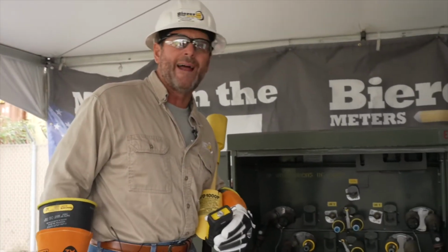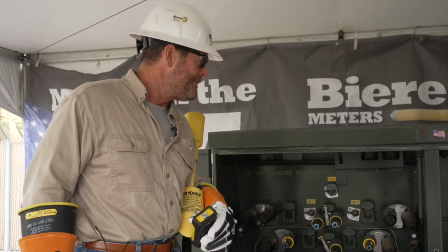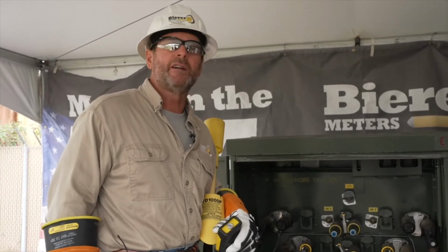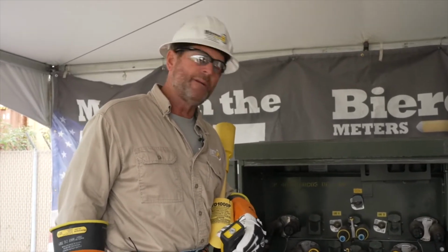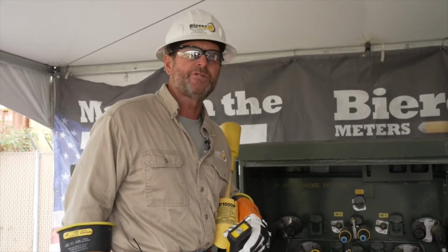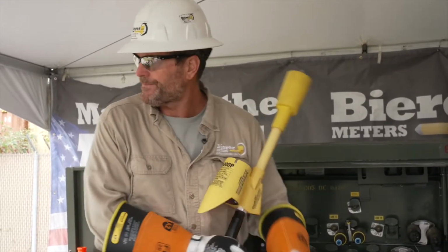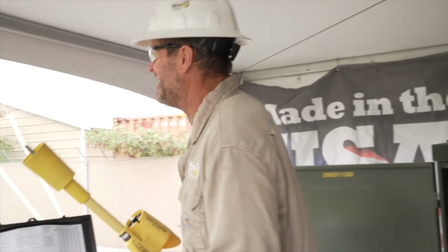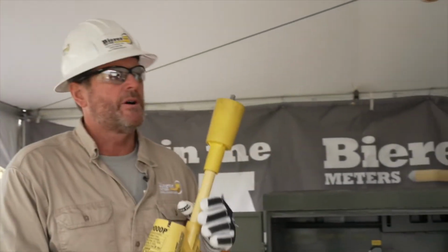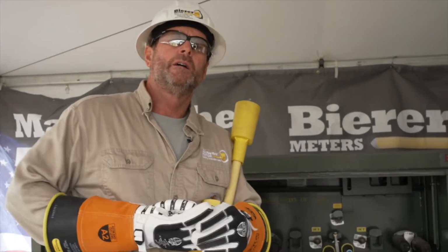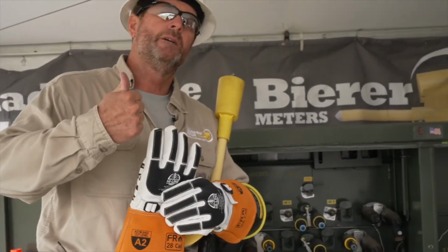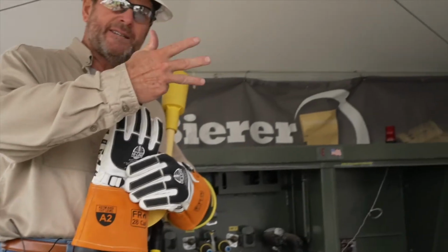Now you can take your TPGs and install your temporary protective grounds. Set up your EPZ, your bracketing, whatever you need to do to protect the equipment and protect yourself. Capiche? Good. All right, good, Abby, you can turn it back on. So that's how we do those five steps: test, open, test, test the tester, ground.